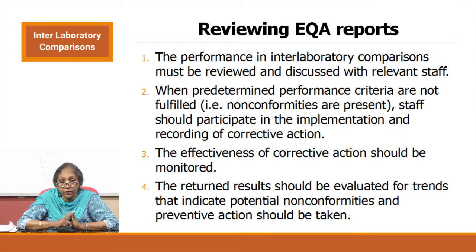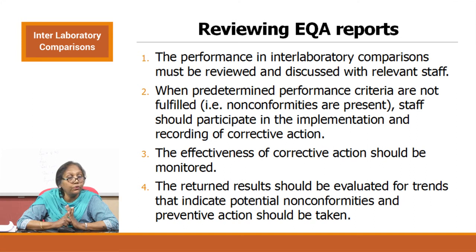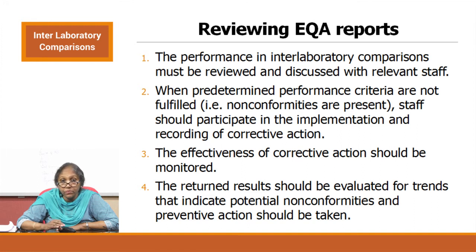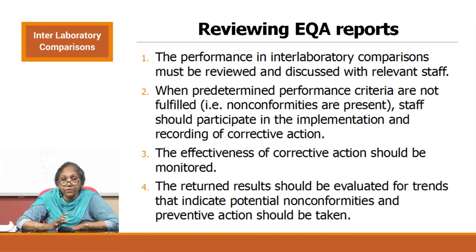Reviewing your EQAS: the performance in interlaboratory comparisons must be reviewed and discussed with the relevant staff — with those who reconstituted the sample, ran the sample, and filed the reports, because mistakes can be hidden anywhere. When predetermined performance criteria are not fulfilled and non-conformities are present, staff should participate in implementation and recording of corrective actions. The effectiveness of corrective actions should be monitored. Results should be evaluated for trends to indicate potential non-conformities so preventive actions can be taken.